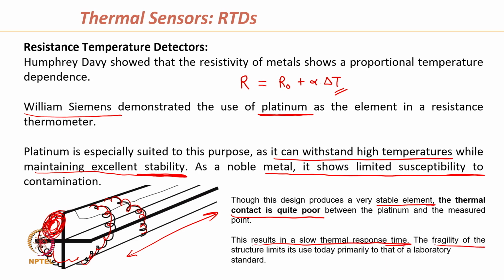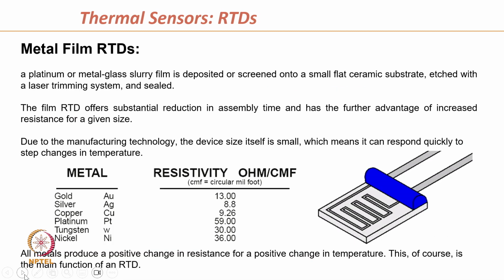The fragility of the structure also limits its use in multiple laboratory environments. So, this type of assembly can give you an RTD sensor, but it is very limited to certain laboratory situations. So, now we switch to thin film RTDs, or the metal film RTDs.